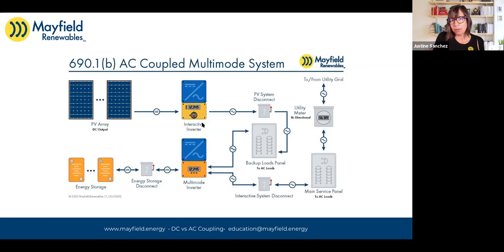As you recall, inverters are designed to shut down when the utility goes down. So while we can keep this inverter in place, its output has to get rewired to essentially a backed up loads panel, instead of going direct to the main service panel.